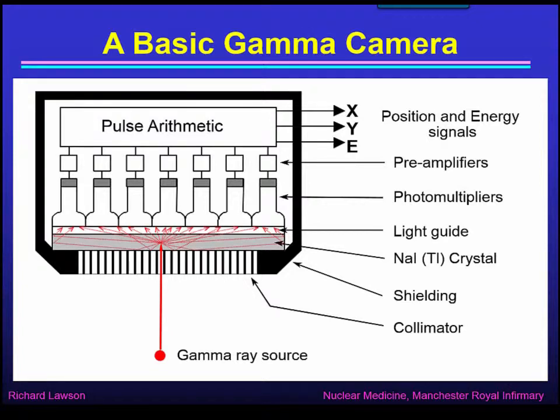Each gamma-ray interacts to give a flash of several thousand visible light photons, which are reflected and channeled out through the light guide to reach the photomultipliers. The signal from each photomultiplier is amplified and passed to the pulse arithmetic circuit, which calculates the energy of the gamma-ray from the total amount of light received, and also x and y coordinates representing the position in the crystal where the gamma-ray interacted.